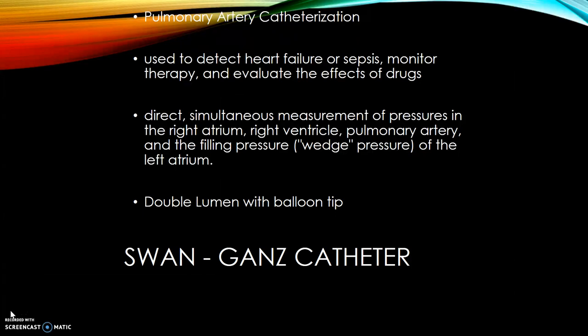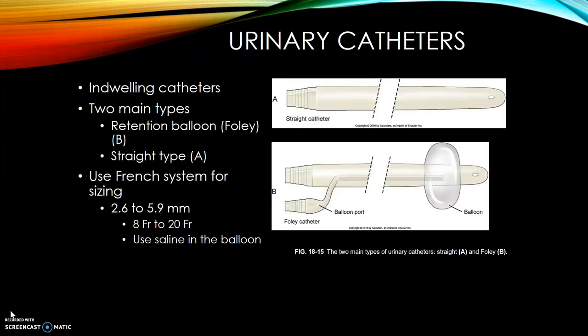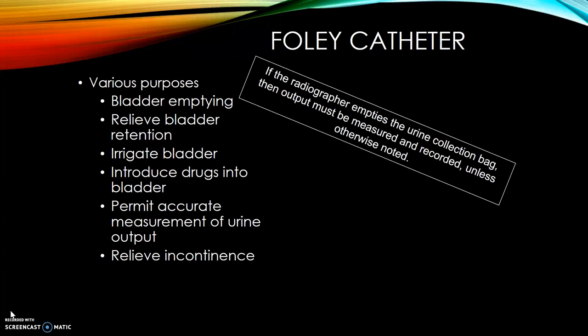The Swan-Ganz catheter is a pulmonary artery catheterization used to detect heart failure or sepsis, monitor therapy, and evaluate the effects of drugs. It provides direct simultaneous measurement of pressures in the right atrium, right ventricle, pulmonary artery, and the filling pressure of the left atrium. It is typically a double lumen with a balloon tip. Urinary catheters are indwelling catheters with two main types: a retention balloon type and the straight type, sized using the French system. The Foley catheter is used primarily for bladder emptying, to relieve bladder retention, irrigate the bladder, introduce drugs into the bladder, permit accurate measurement of urine output, and relieve incontinence. If the radiographer empties the urine collection bag, output must be measured and recorded unless otherwise noted.